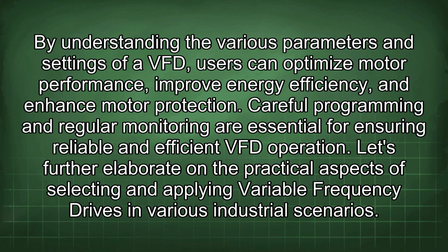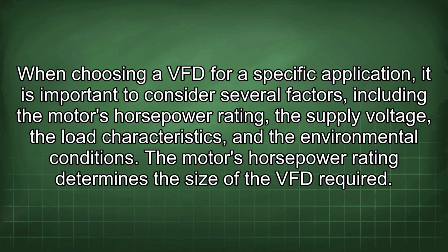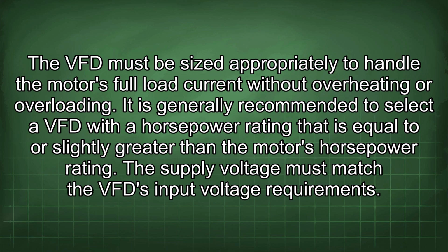Let's further elaborate on the practical aspects of selecting and applying variable frequency drives in various industrial scenarios. When choosing a VFD for a specific application, it is important to consider several factors, including the motor's horsepower rating, the supply voltage, the load characteristics, and the environmental conditions. The motor's horsepower rating determines the size of the VFD required. The VFD must be sized appropriately to handle the motor's full load current without overheating or overloading. It is generally recommended to select a VFD with a horsepower rating that is equal to or slightly greater than the motor's horsepower rating. The supply voltage must match the VFD input voltage requirements.